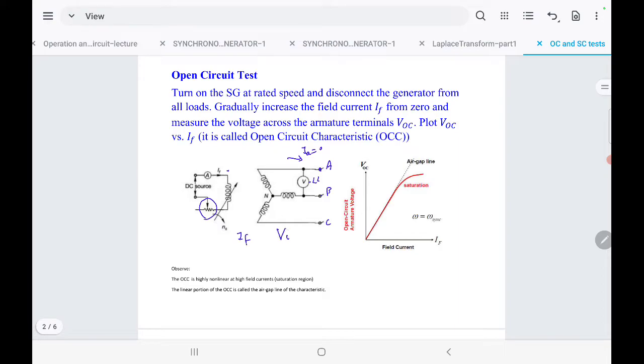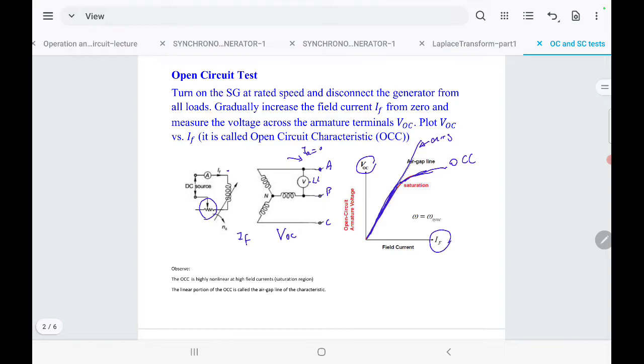By varying IF we get values for the open circuit line-to-line voltage, and we can sketch the relationship between the open circuit voltage and field current — this is the magnetizing curve. It is almost a straight line in the beginning, then after the knee of the curve it starts to saturate and becomes nonlinear. If you extend the straight line portion, that represents the air gap line — an approximation assuming no iron saturation.